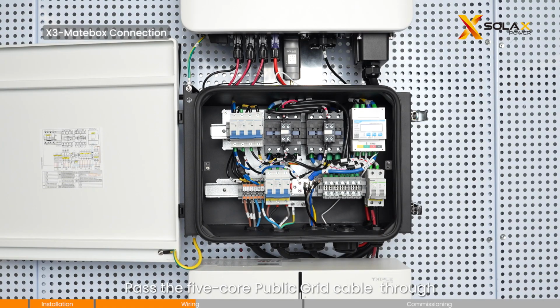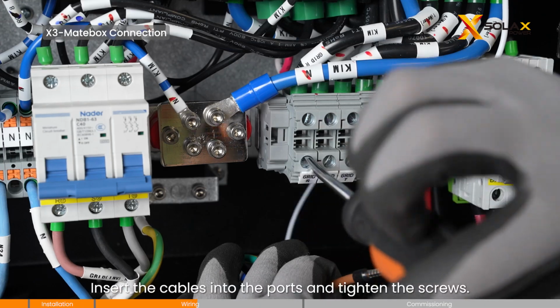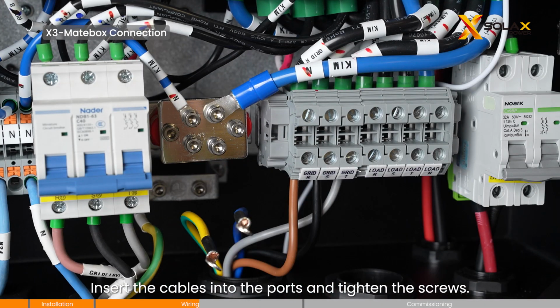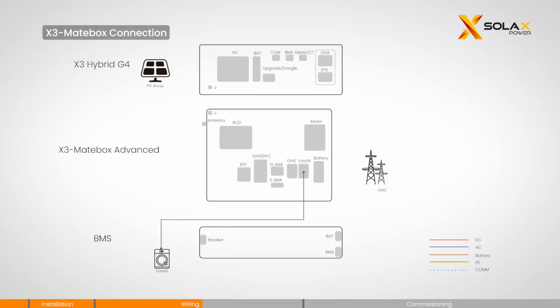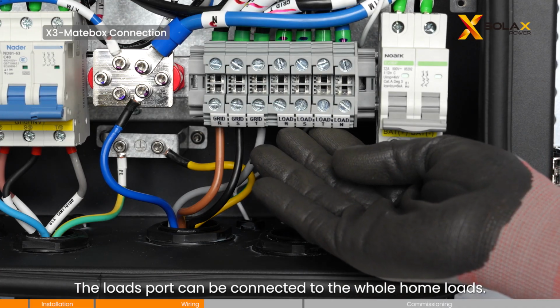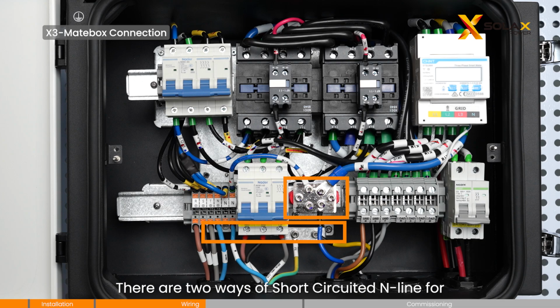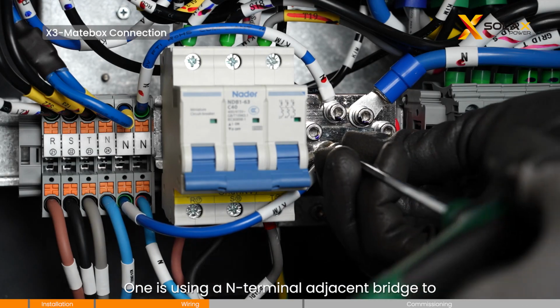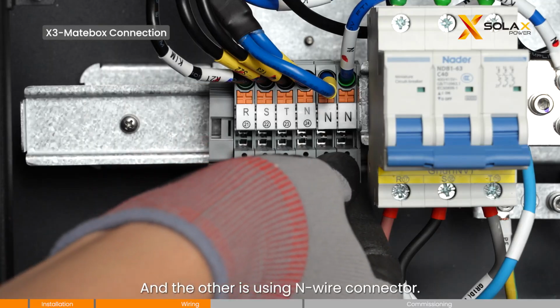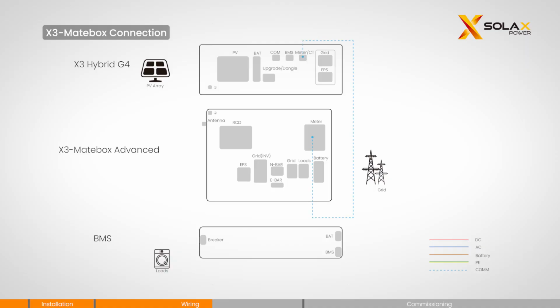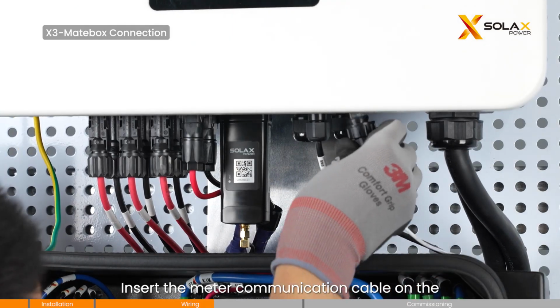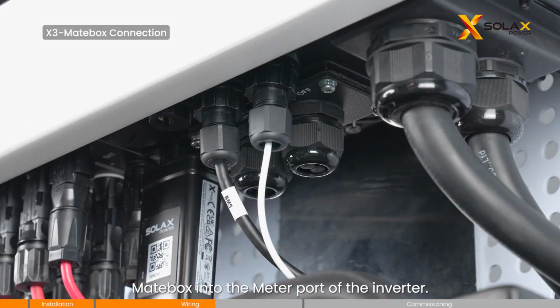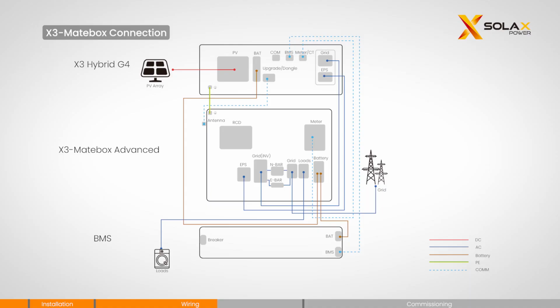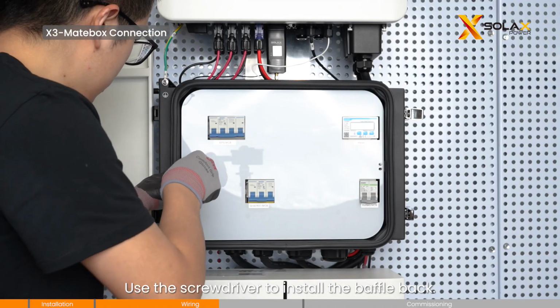Pass the 5-core public grid cable through the grid waterproof plug. Insert the cables into the ports and tighten the screws. The loads port can be connected to the whole home loads. There are 2 ways of short-circuited N-line for Australia and New Zealand regulations. One is using an N-terminal adjacent bridge to connect the N ports, and the other is using N-wire connector. Insert the meter communication cable on the matebox into the meter port of the inverter. Use the screwdriver to install the baffle back.